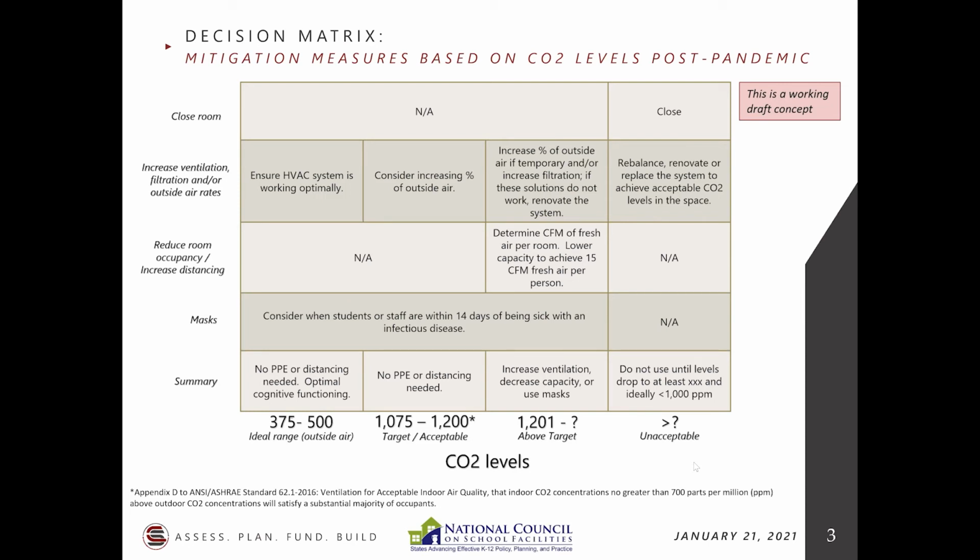The other thing is, if you had 100% outdoor air, you've got a lot of fresh air. The air cleaner is going to have to be able to compete with that, and if you cannot compete with your outdoor air, it's not going to do any good. So optimally, air cleaners are used where you don't have the ability to bring in a lot of outdoor air. But if you're already ventilating as best you can, they may not be as effective as you would hope they would be. Well, that's important to understand. That's interesting.